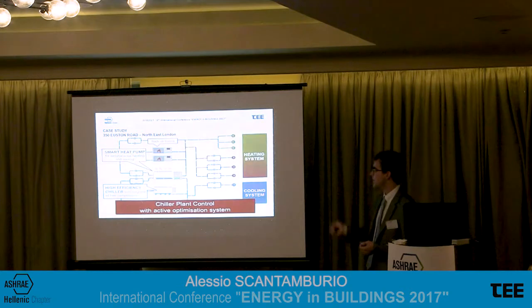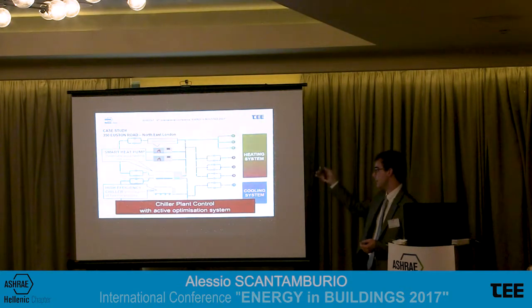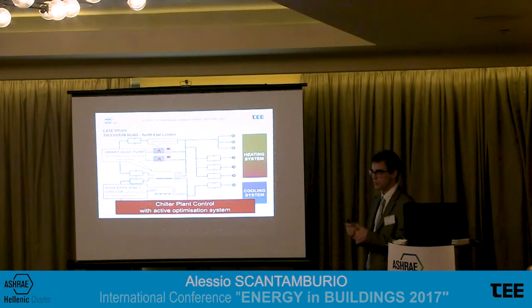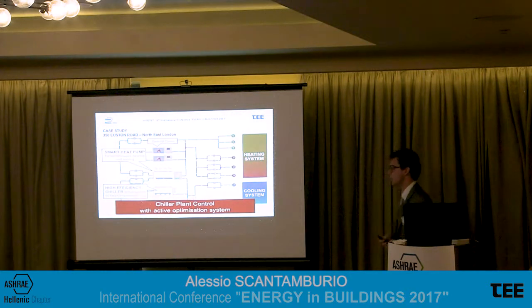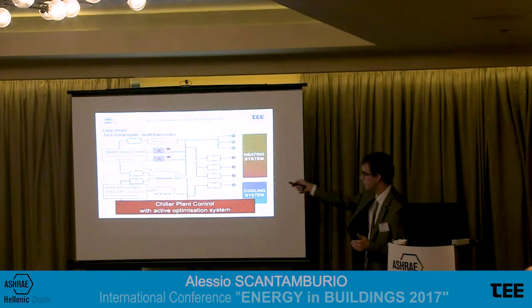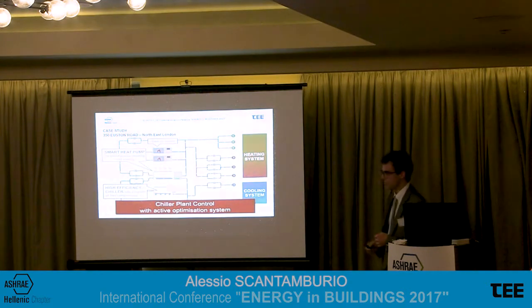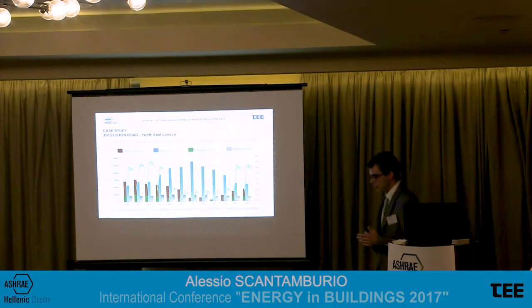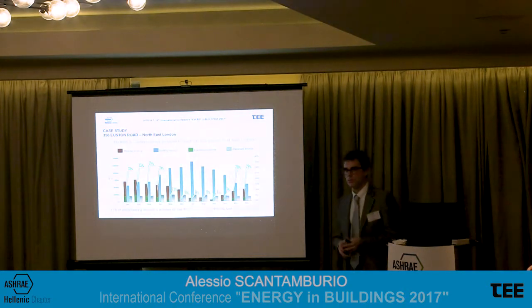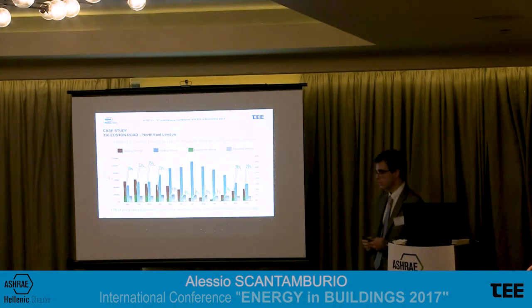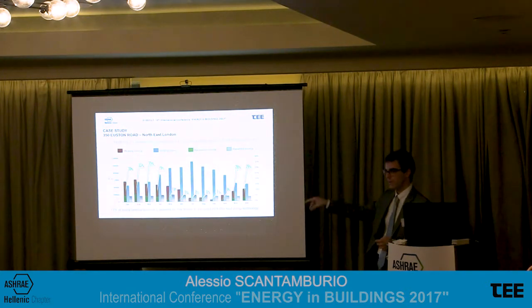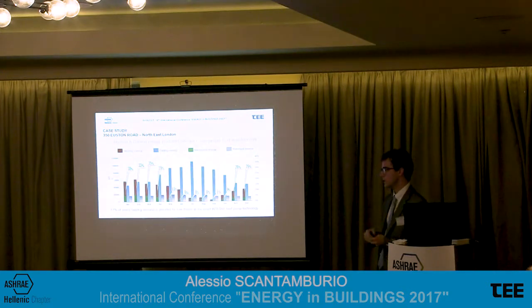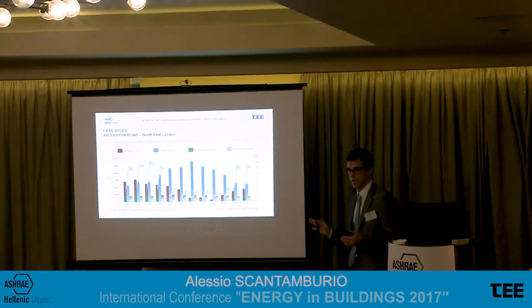Okay, and everything is managed through plant control with an active optimization system, which takes into account the real efficiency of the unit, and which is the best combination of chiller, heat pump, and backup boilers. Okay, as said, we obtained very good results from the simulation, honestly. But these are the real numbers after 1 year of operation, 1 year of monitoring the unit. This is not a simulation, these are real numbers.